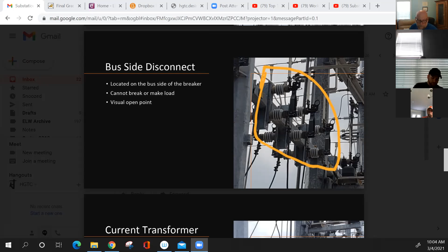Anytime you're asked to go in a substation, you might have to work on that breaker or the regulator, something in there, and you have to kill the power to be able to work on it, de-energize it. You have to flag and tag each one of these disconnects. There's 3 of them on this side, 1, 2, 3. There's 3 on the back side, 1, 2, 3, and you have to actually put tags on them to let somebody know, hey, this switch is out of service. It also serves as a reminder to you, hey, I can work on this equipment safely. I've got 2 visual opening points.